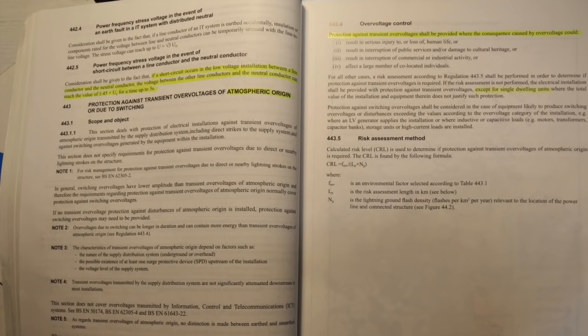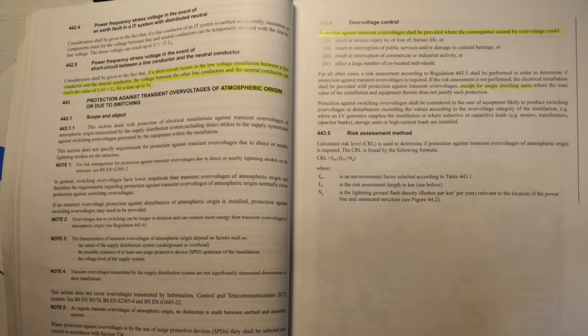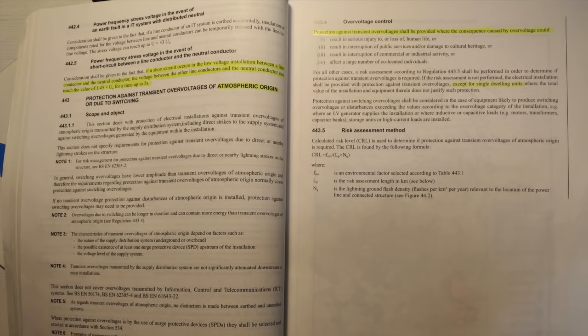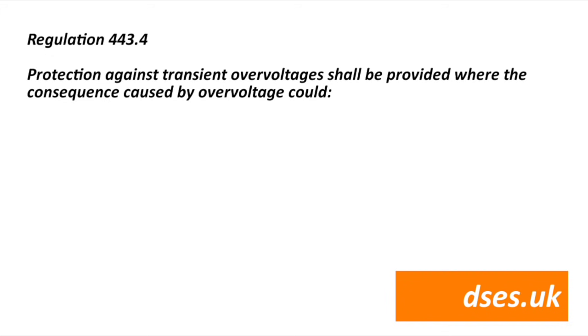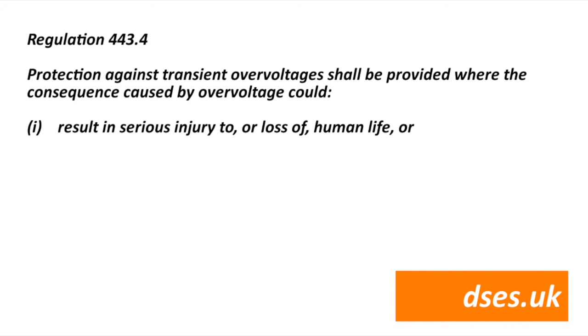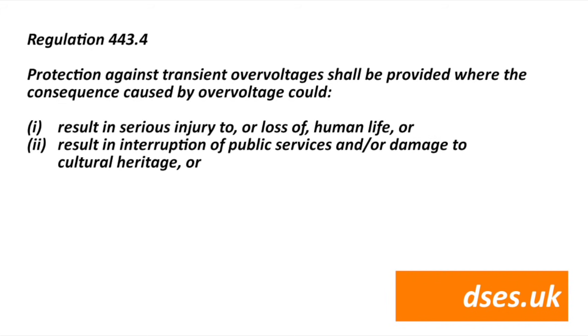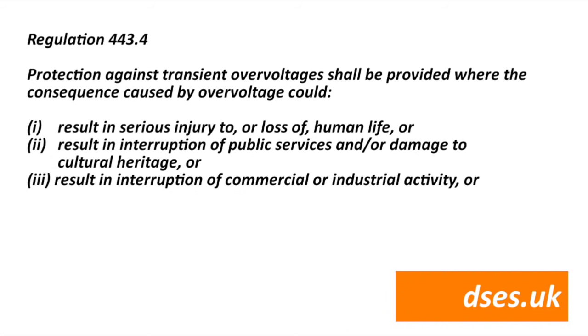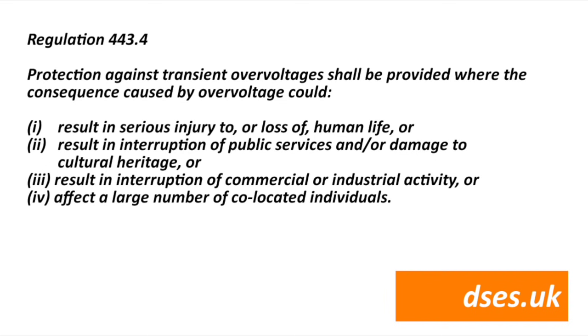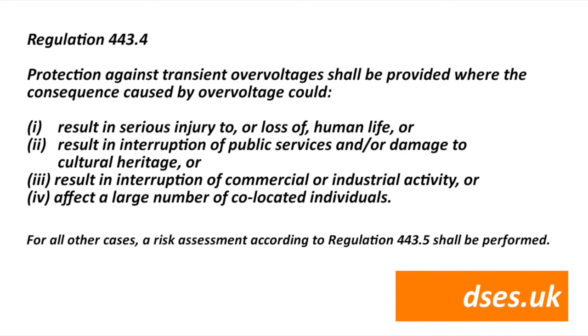But as 18th edition bites in, am I actually required to be installing these things for my clients as a matter of course? Well, let's quickly look into that before we get the screwdrivers out. Regulation 443.4 states, protection against transient overvoltages shall be provided where the consequence caused by overvoltage could result in serious injury to or loss of human life, or result in interruption of public services and/or damage to cultural heritage, or result in interruption of commercial or industrial activity, or affect a large number of co-located individuals. For all other cases, a risk assessment according to Regulation 443.5 shall be performed.